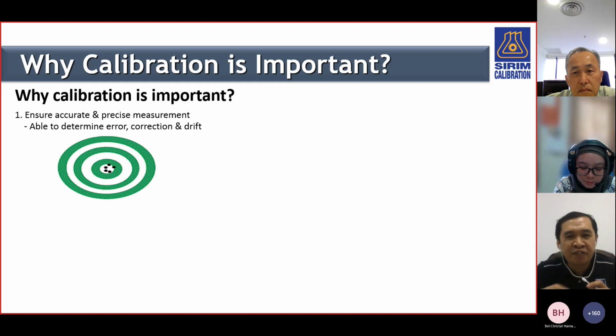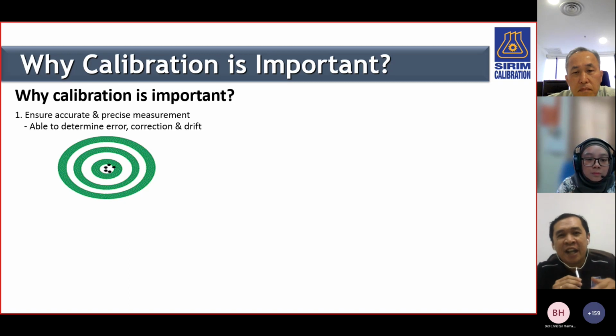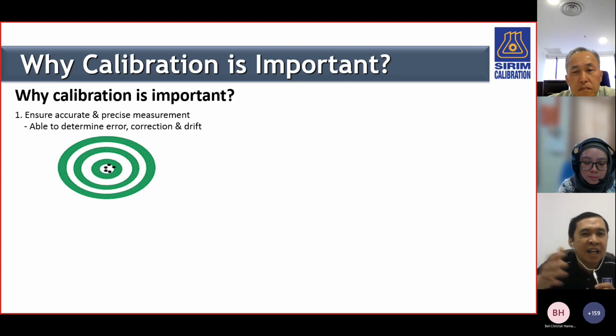As well as the drift - drift is to ensure that you understand your equipment's characteristics. From this drift, you can determine how much the reading has changed from last year until this year, and it's better if you can do your own maintenance. If you have your calibration certificates, you can create your own drift record, maybe from data from the past 5 years until now.